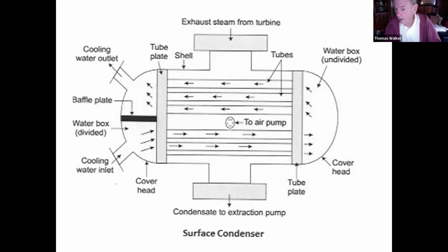And for years around here, one of the most common was what they called a surface condenser. A surface condenser has water inside the tubes and steam from a turbine on the shell side. We use surface condensers to condense large quantities of steam, usually the exhaust from a steam turbine.